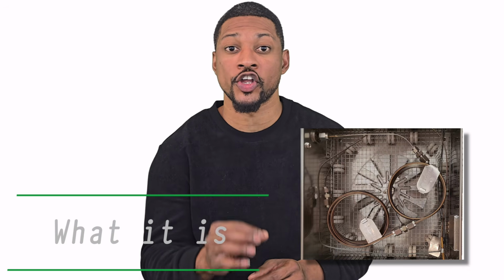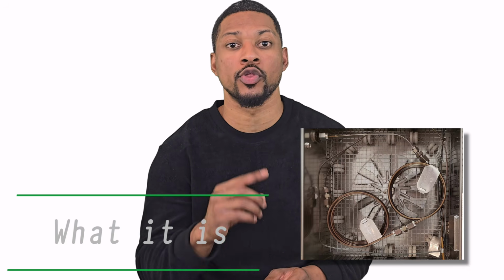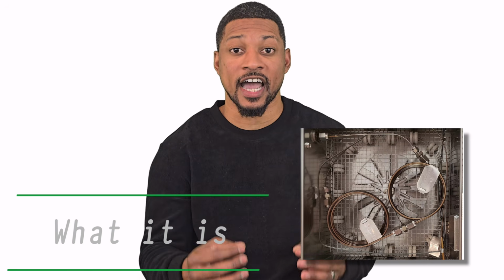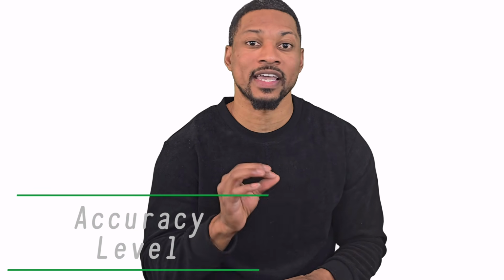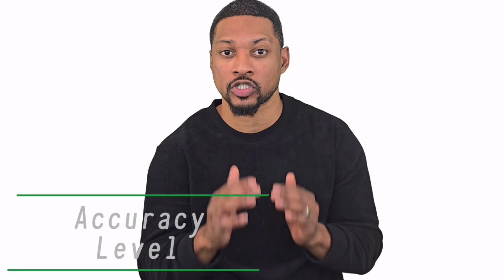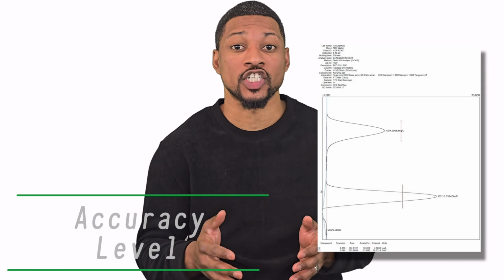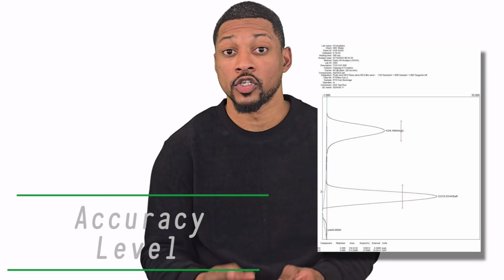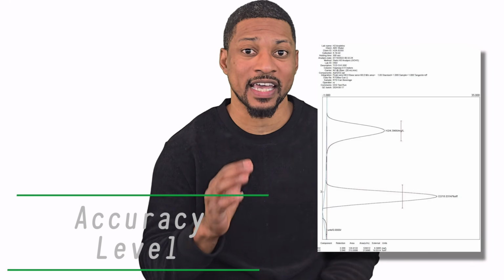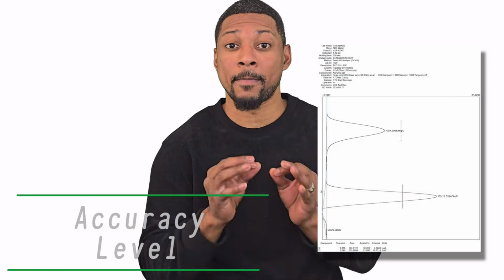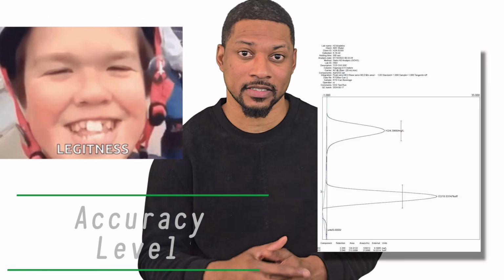Inside the machine, an inert carrier gas pushes the sample through the long column. This column separates hydrogen from everything else. At the end, a thermal conductivity detector sees hydrogen as a tiny change in heat flow. GC delivers traceable, calibrated, and highly accurate results in milligrams per liter. You get an actual hydrogen peak on a chromatogram. You'll see the conditions, the calibrations, and the standards used. This is about as legit as hydrogen testing gets. GC can even pick up dissolved hydrogen gas and quasi-dissolved hydrogen gas.